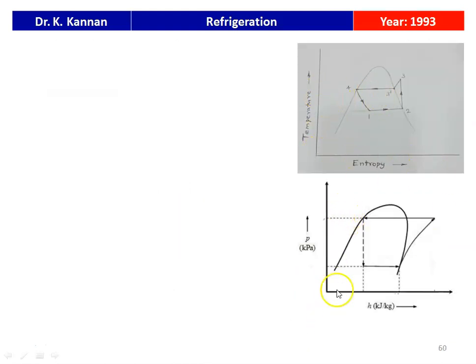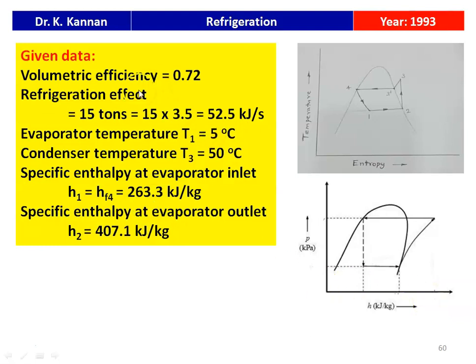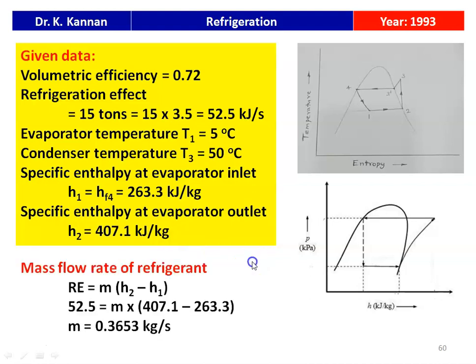Given data: volumetric efficiency = 0.72, refrigeration effect = 15 tons = 52.5 kJ/s, evaporator temperature T1 = 5°C, condenser temperature T3 = 50°C. H1 (evaporator inlet) = HF4 = 263.3 kJ/kg; H2 (evaporator outlet) = 407.1 kJ/kg. Mass flow rate of refrigerant from refrigeration effect: RE = m × (H2 − H1), so 52.5 = m × (407.1 − 263.3), giving m = 0.3653 kg/s.